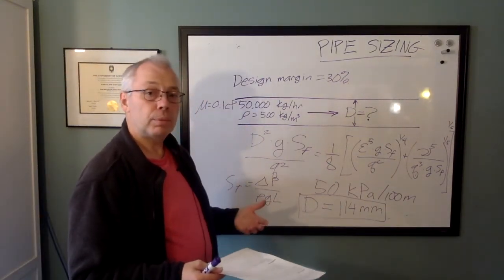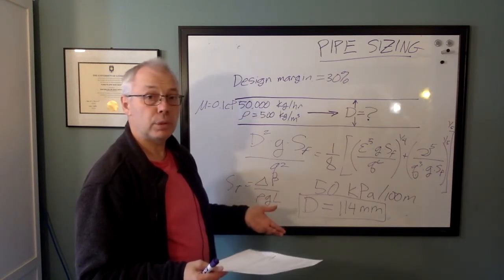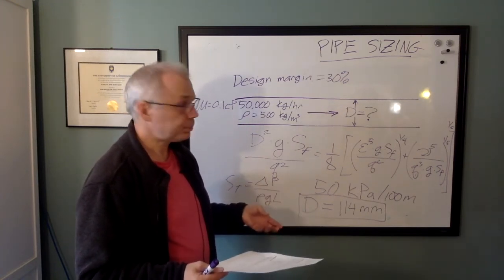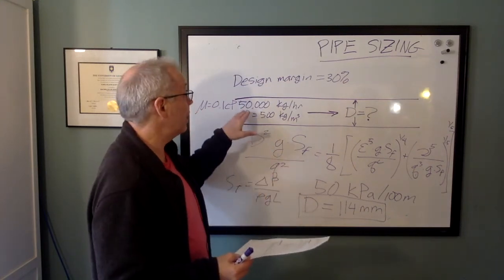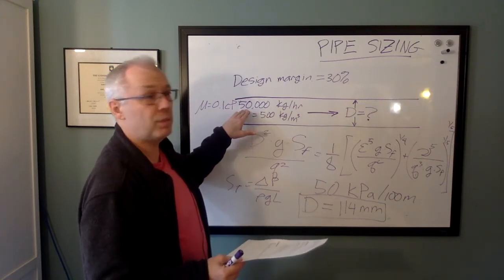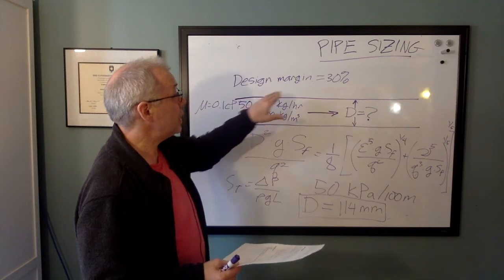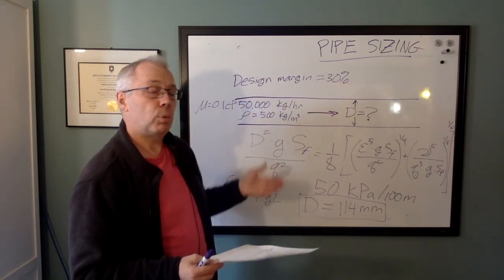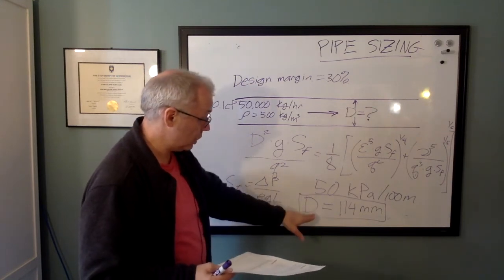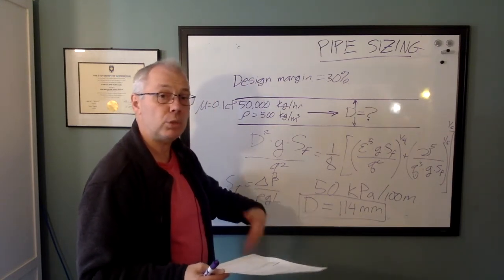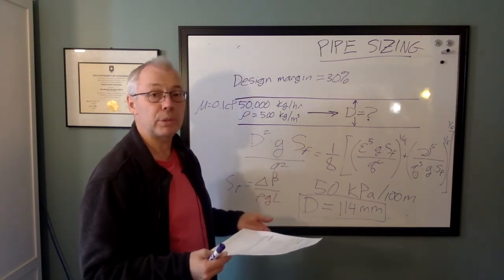And this says that our 4-inch line with an ID of 100 millimeters is too small in this application. It might be okay for the original design if we have only a flow rate of 50,000 kilograms per hour going through it, but our future design case where we need some more flow rate, the 4-inch line isn't good enough, it's not big enough. So that means we need to go up to 114, so we'll go to the next line size. So instead of a 4-inch, that's a 6-inch line, so 150 millimeters ID.